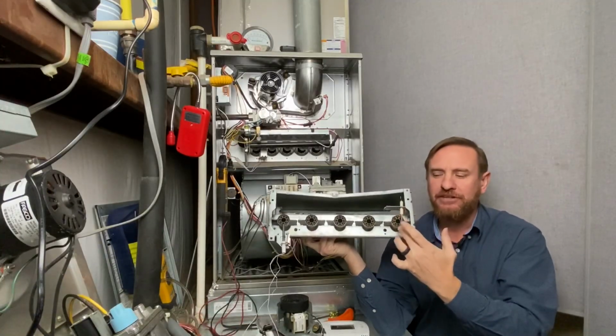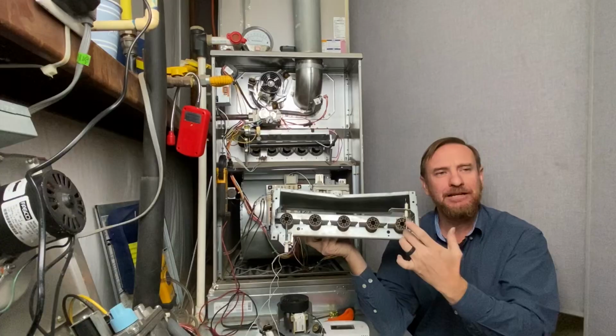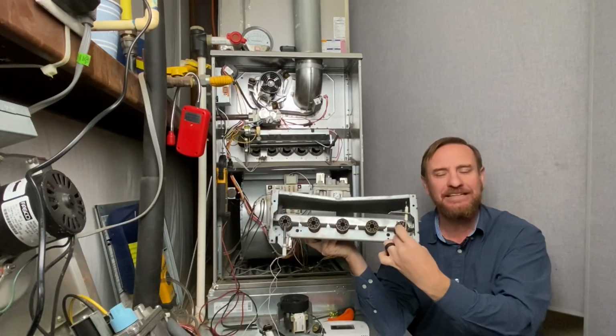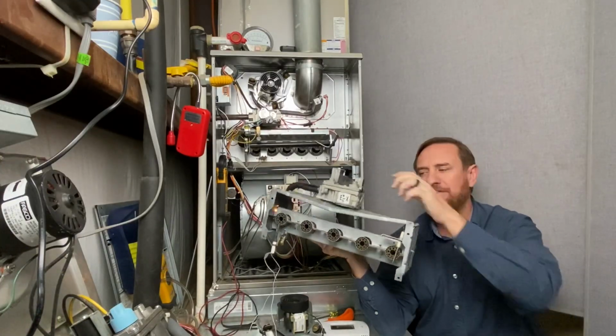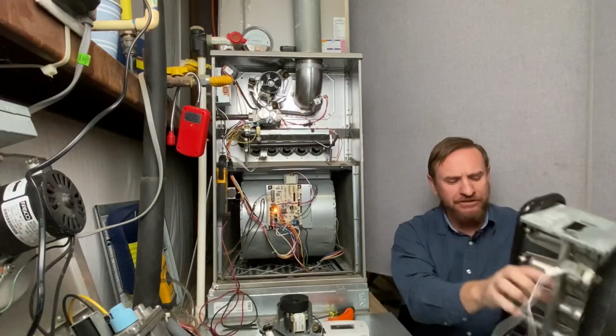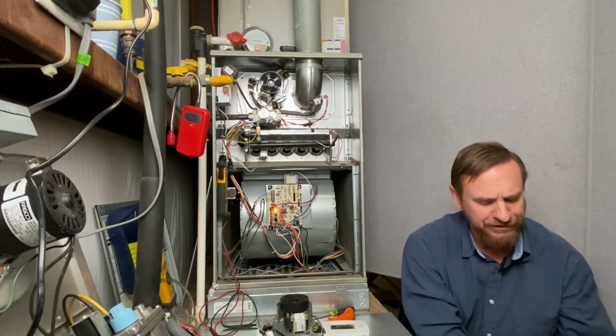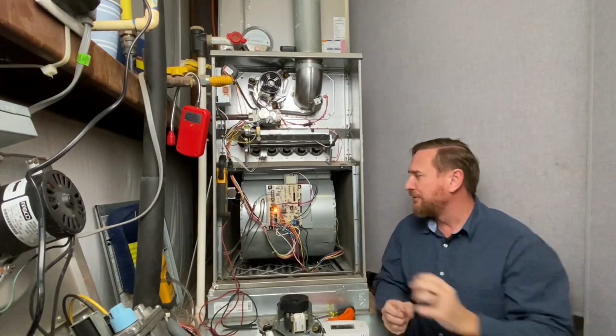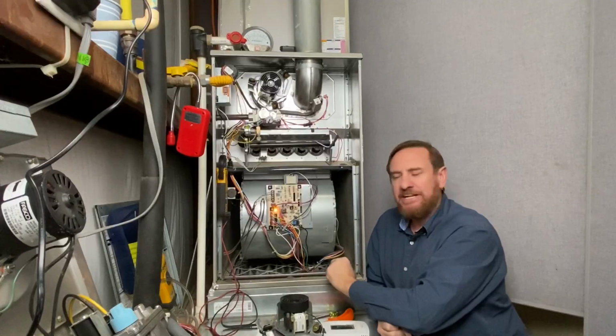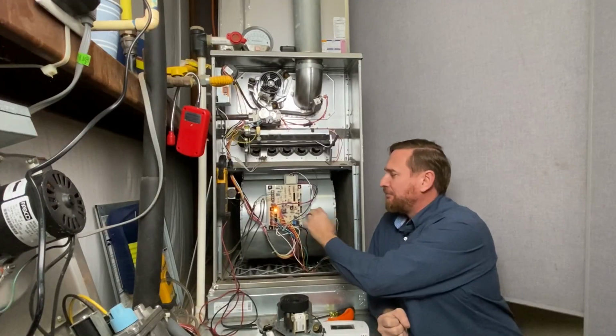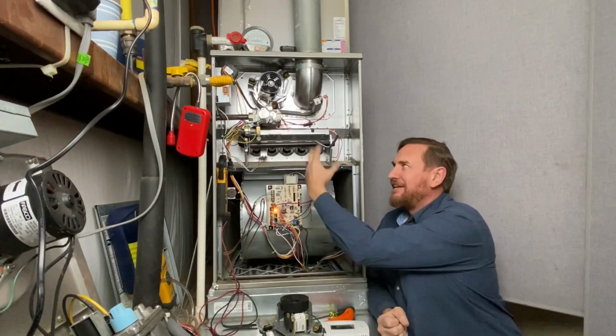This is one of your most common service calls for heating. This flame sensor gets dirty, it has to be cleaned. There's a special way of doing that. We'll save that for another video as well. So once we've proven a flame through flame rectification, the heat exchanger is allowed to heat up. Then it's going to energize the blower, and all these relays on here energize all these different things.